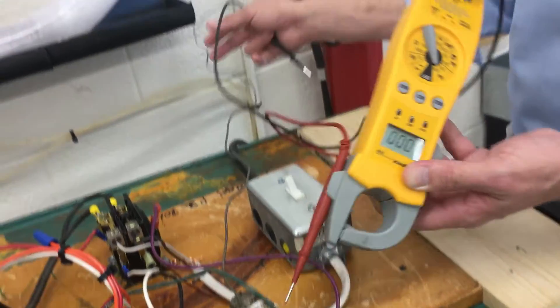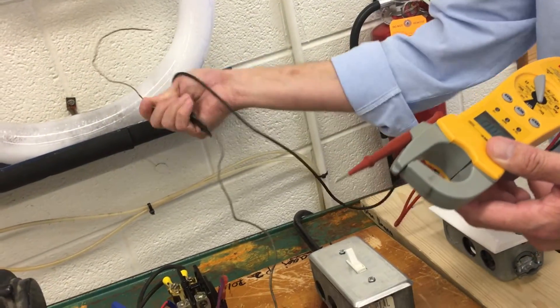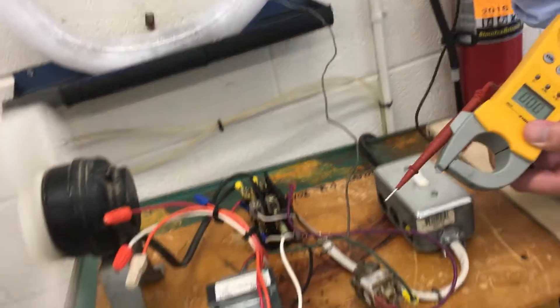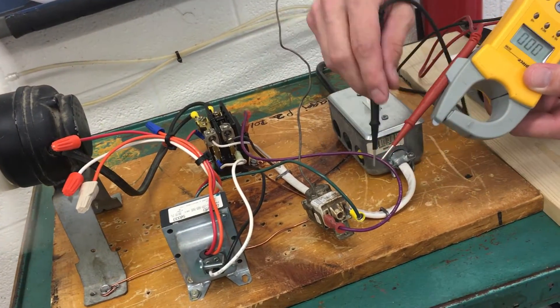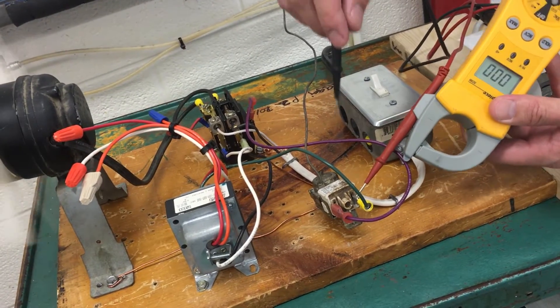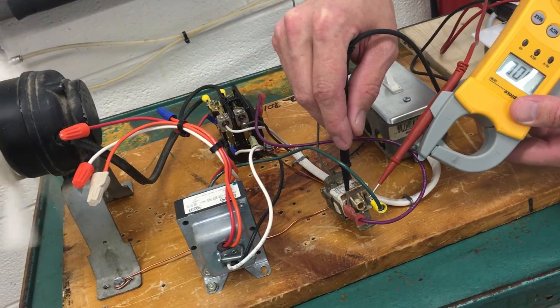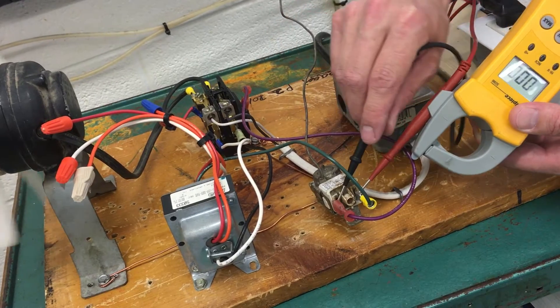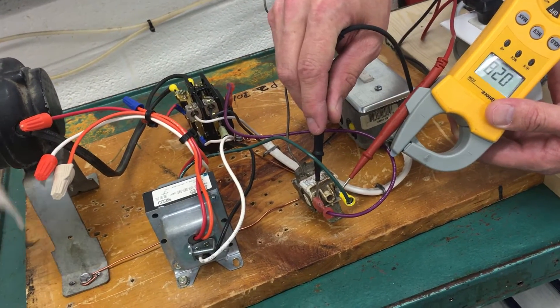If I wait until the thermostat satisfies, then I can measure it again, and we can measure the difference in potential because now we're reading through this coil and all the way back to the transformer on the one side. And it will still show, it should still show 24 volts. There it is, 27 volts.